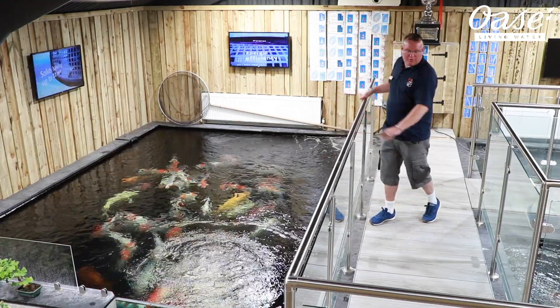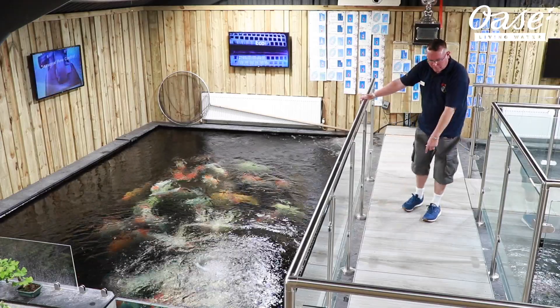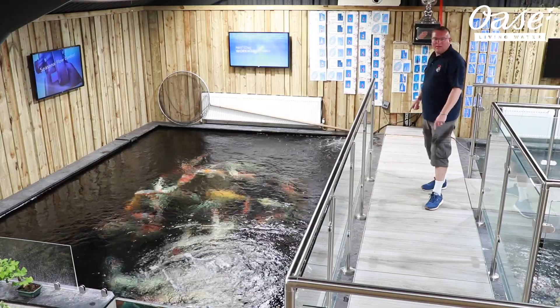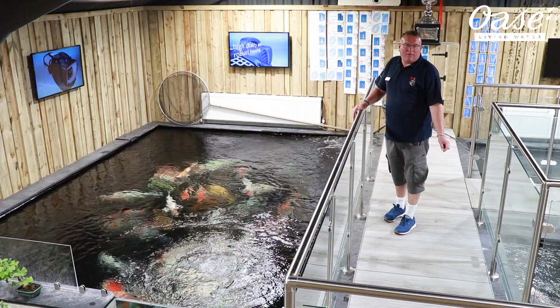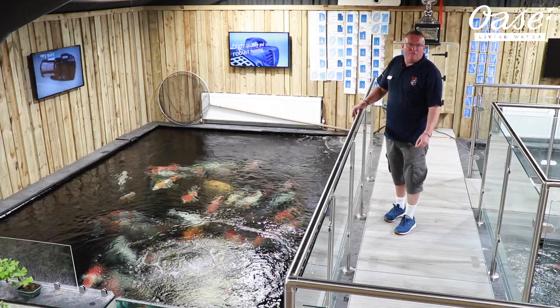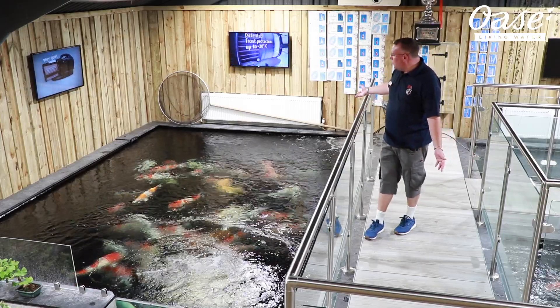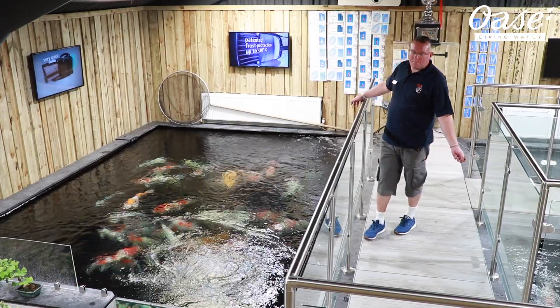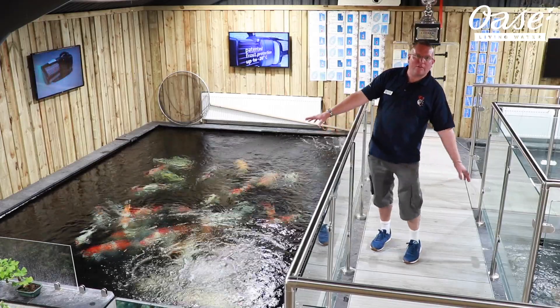The pond is fed by four 4-inch bottom drains located centrally in a line along the bottom of the pond. Those feed into two Compact L Oasi drum filters, one approximately here, one here, both underneath our tiled flooring. Each is powered by an Oase Aquamax Expert 21000 through an Oase UV system. The reason we went for that was mainly because of the quality of water we achieve with the drum, which is paramount with these massive viewing windows, one of the wow factors of our new shop.